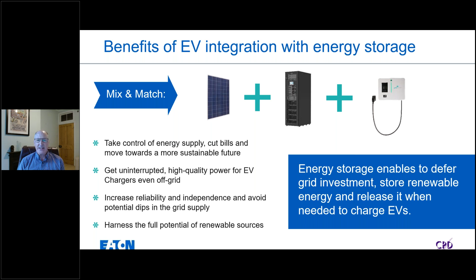What is the efficiency or losses in an average battery storage system? It depends where you look. Converter efficiencies are typically 96 to 97%, but what we usually look at is round trip efficiency, meaning if you put one kilowatt-hour into a battery and then deliver that energy back out to a load, how much do you get. Typically you see around 85 to 90% round trip efficiency.